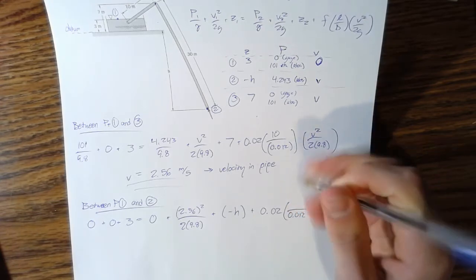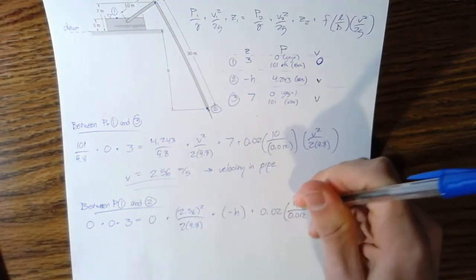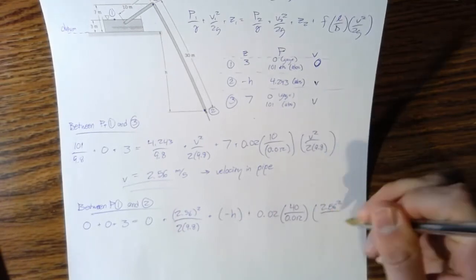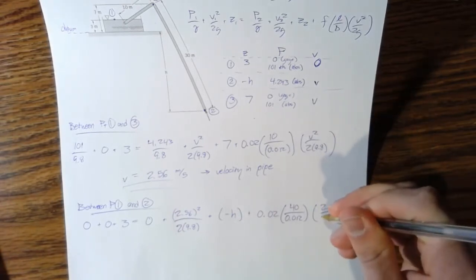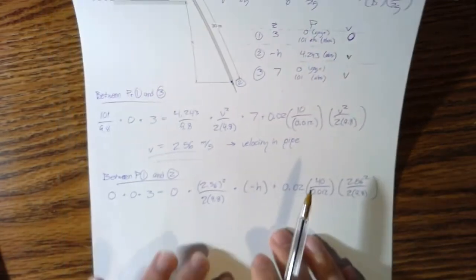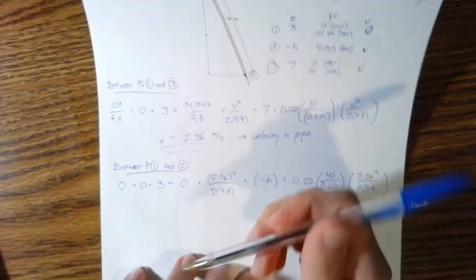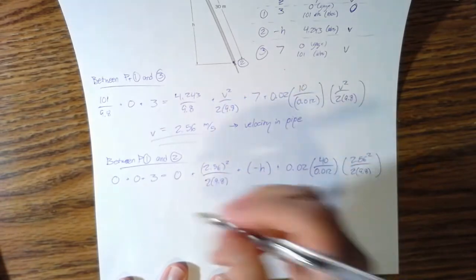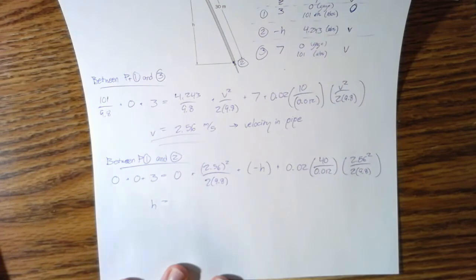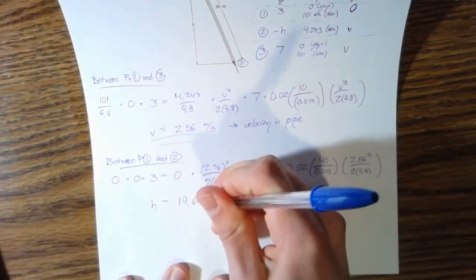Then we have the same friction factor multiplied by, same diameter, but this time the length is 10 plus 30, 40 meter length, the velocity that we just calculated, 2 times 9.8. Now this is just add this over, subtract 3, multiply everything out, have your calculator do all the heavy lifting, and you'll get h is equal to 19.6 meters.